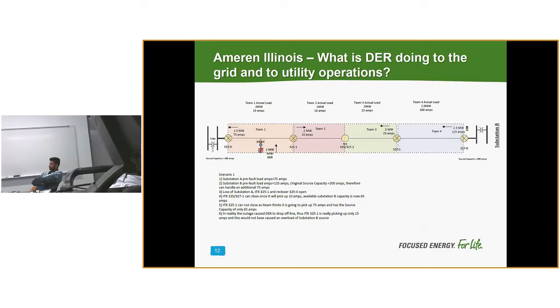So when I have a fault condition on A, this source now is going to think I have 75 amps plus 10 amps, so 85 total amps that I need to pick up. Where this can only handle, in this case, 75 amps. So just a different source, different data point. It could handle 75 amps, but it thinks it needs to handle 85 amps, when in reality it does not need to handle 85 amps. I don't have enough load here. I'm actually backfeeding. So I should be able to handle this entire load easily. So I just wanted to bring some real scenarios, real data of what we've got here that are impacting our DA schemes.